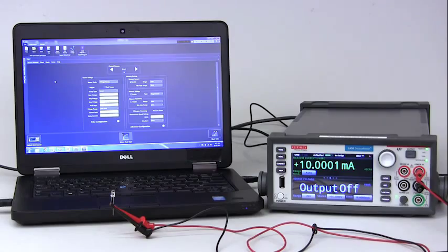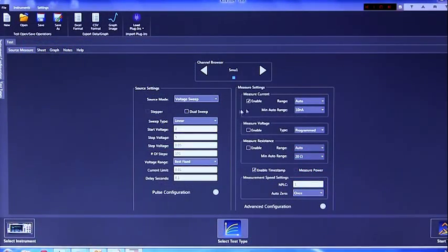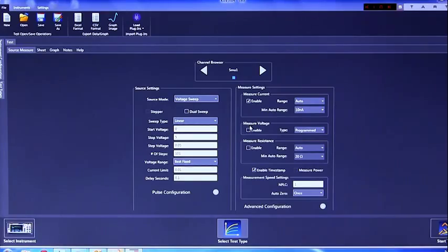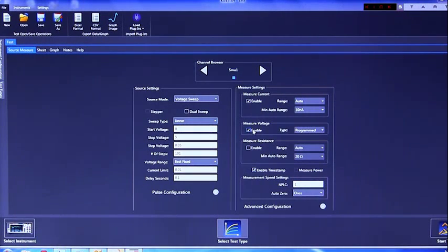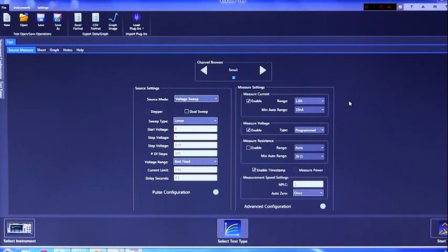To get an IV curve, you will have to make sure that you have measured current selected and measured voltage selected. With measured voltage, you want to make sure that you have it programmed rather than measured.